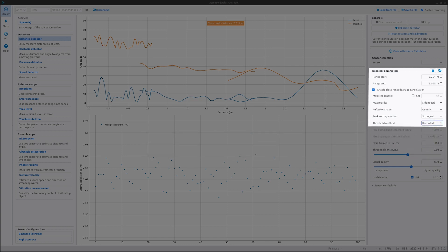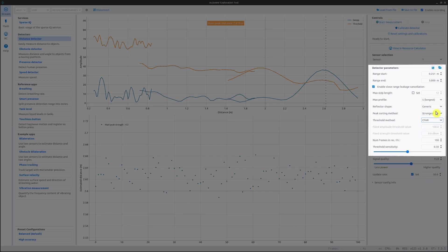The last option is the CFAR threshold. This threshold method constructs a threshold for a certain distance by using the signal from neighboring distances of the same sweep. This requires that the object gives rise to a single strong peak, such as fluid surfaces, and not, for example, the level in a large waste container.